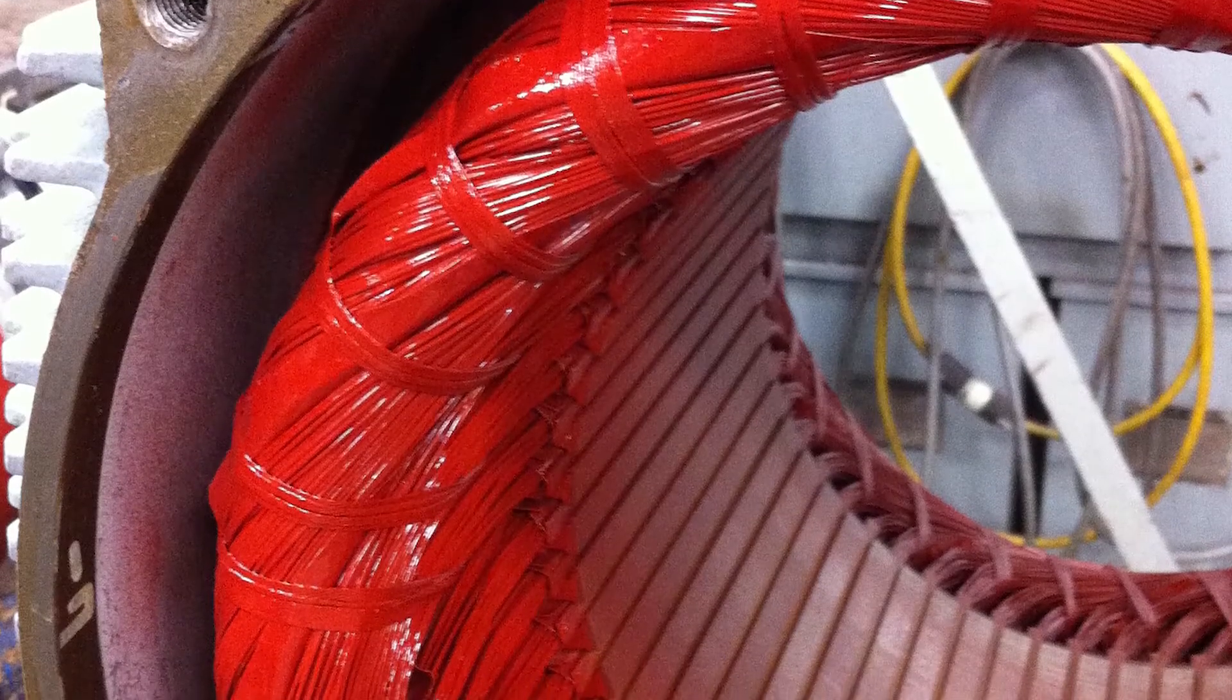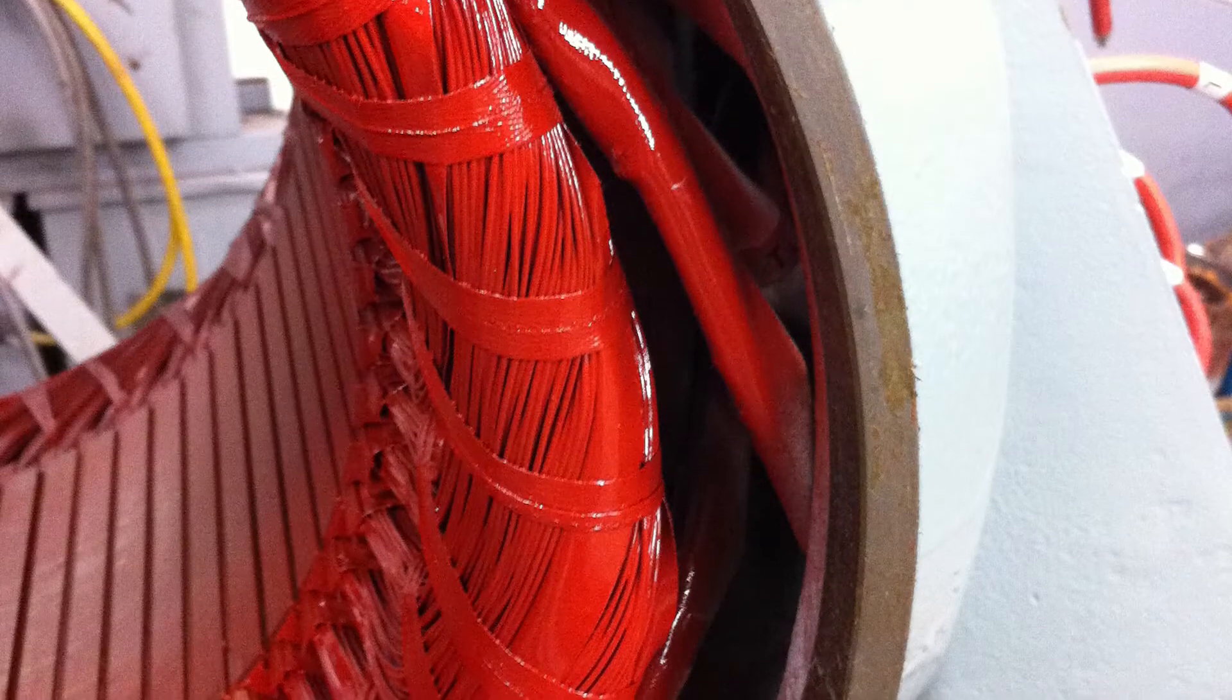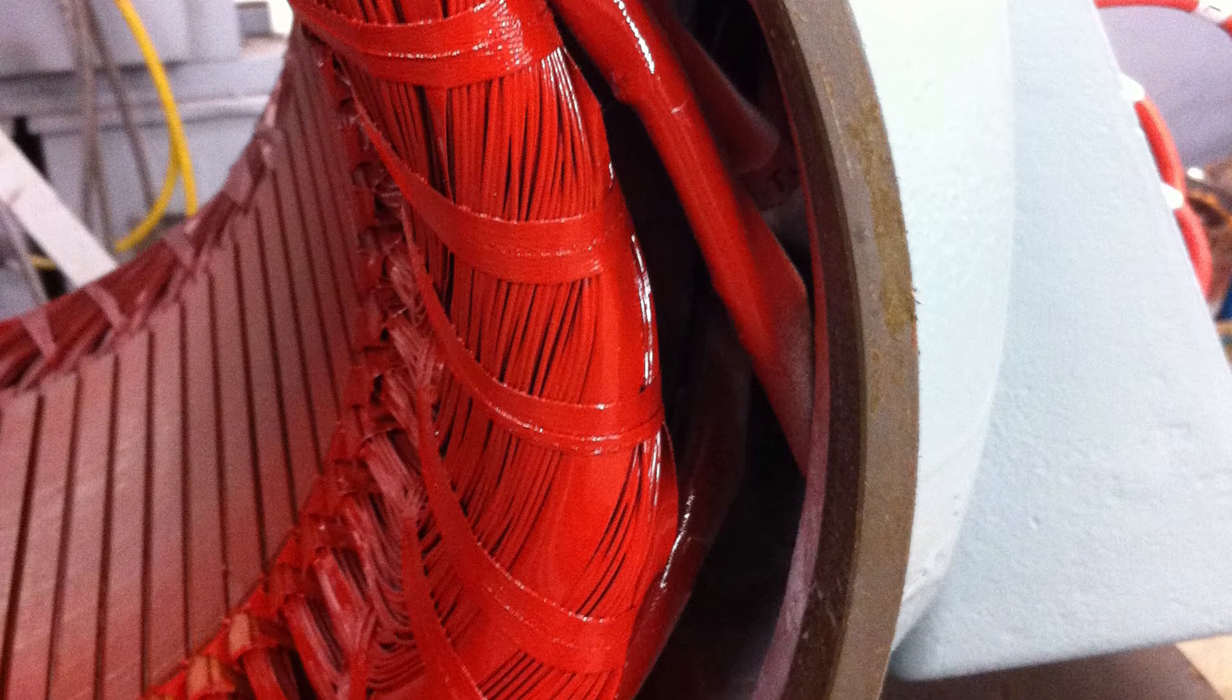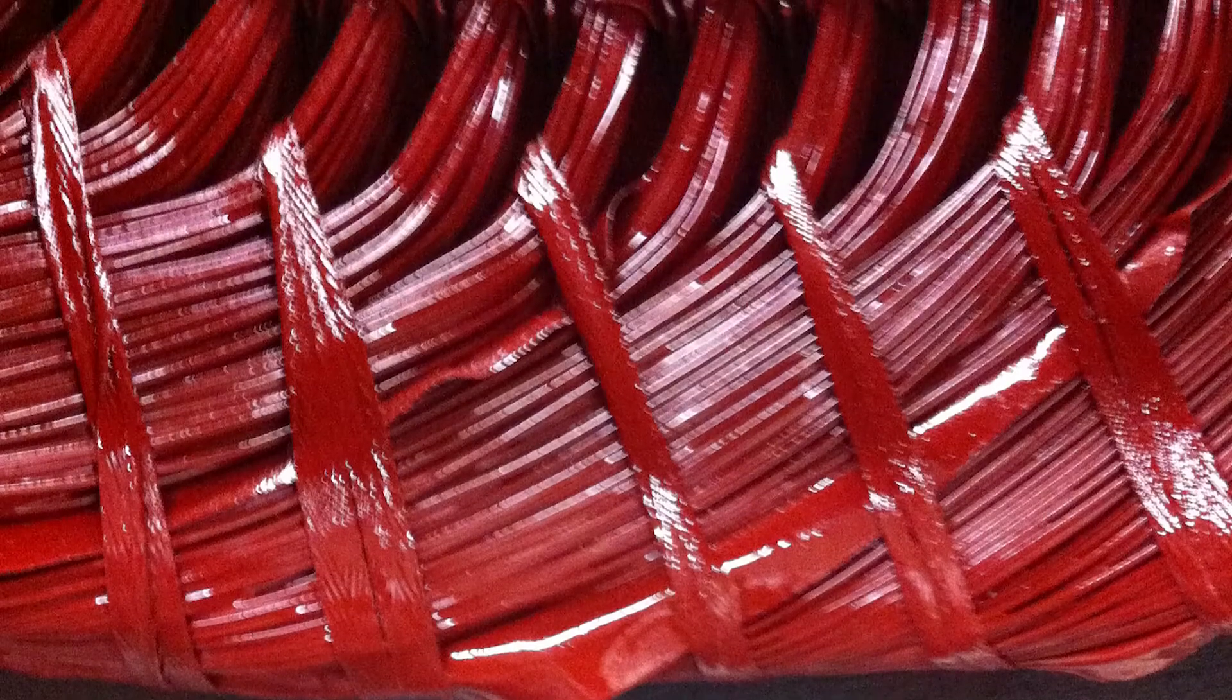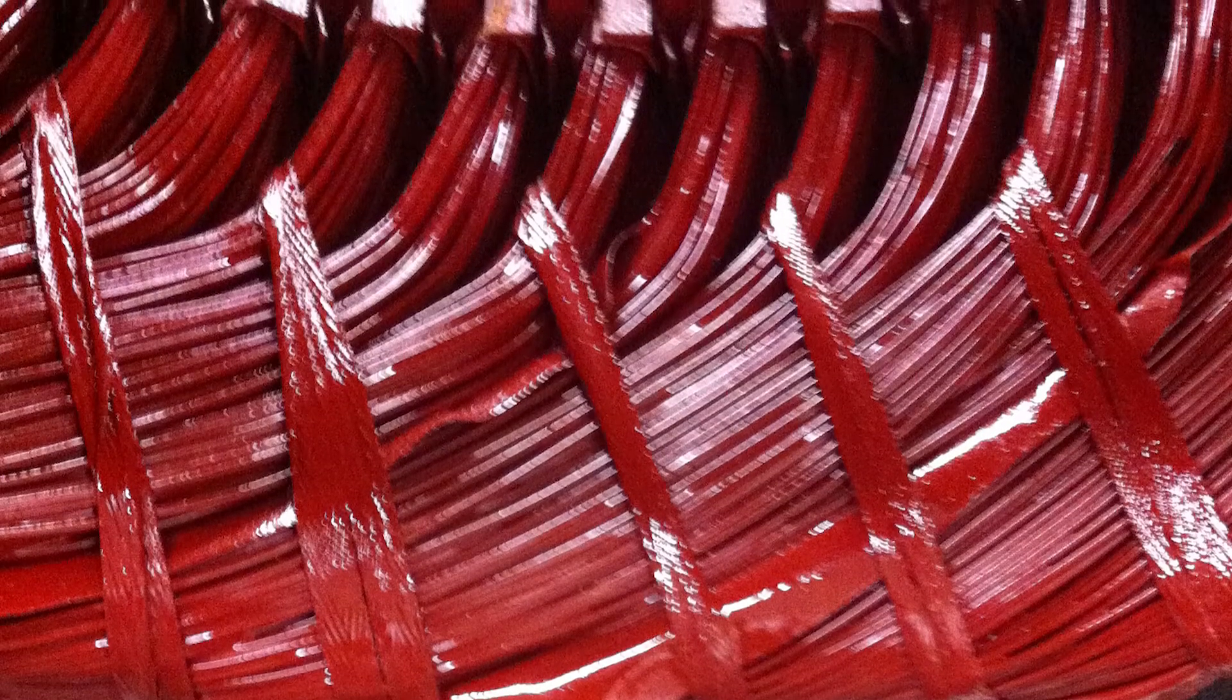Class F insulation with Class N varnish allows use in higher ambient conditions. Inverter shield insulation system with spike-resistant inverter grade magnet wire that meets or exceeds NEMA MG1 Part 31.